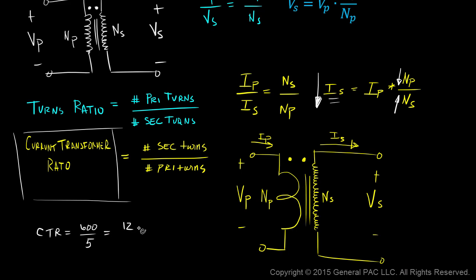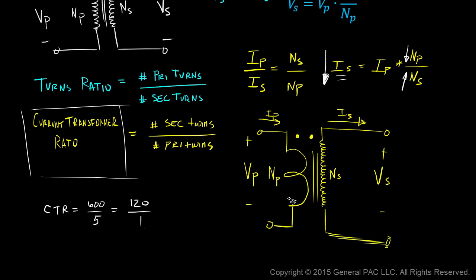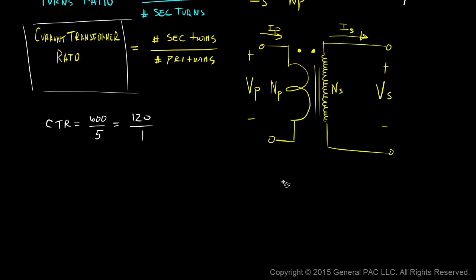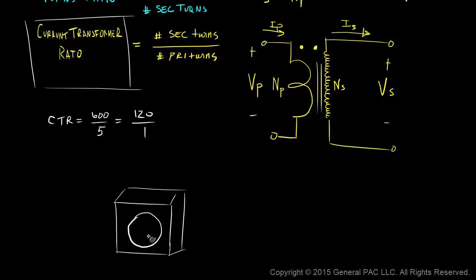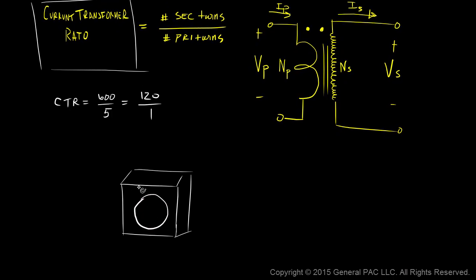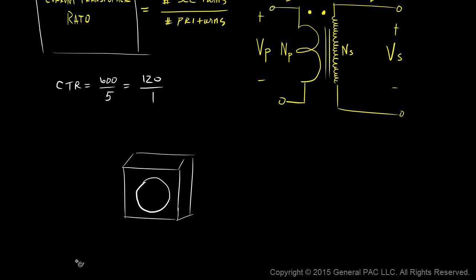Another way to express 600:5 is 120 to 1 — meaning 120 secondary turns and only 1 primary turn. A type of current transformer called the window-type current transformer has a large window, and a conductor flows directly through it, with the source on one side and the load on the other.